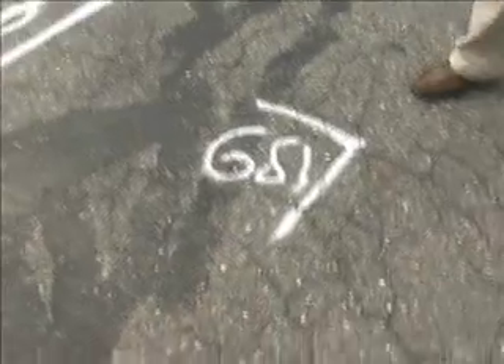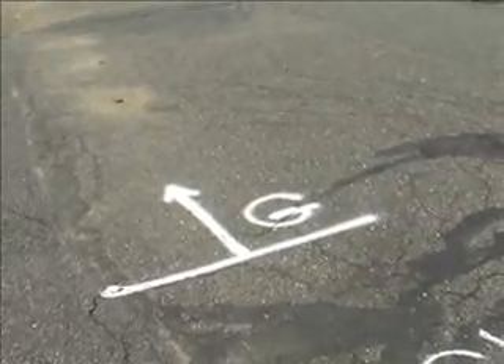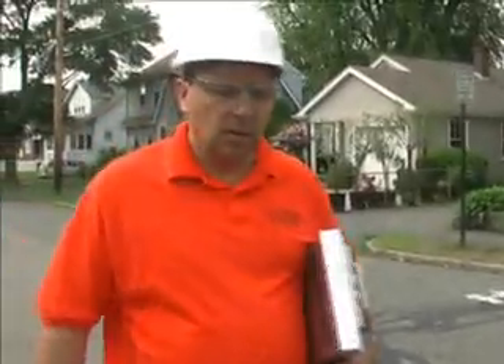We're going about 18 inches deep. These are markings from when you found the leak? Correct. Gas Safety Inc., GSI, and National Grid also marked out. This shows the range where you think the leak is — in between these white markings. The gas company drilled holes in a series, taking gas readings in each one to determine where the high point of the leak is. We're not here to pinpoint the leak; we're here to determine if this gas is affecting the tree. National Grid is here to determine the extent of the leak and whether it's safe to leave. They've decided it's safe enough to leave the leak. I'm here to document that there is gas near the tree that's damaging the tree.